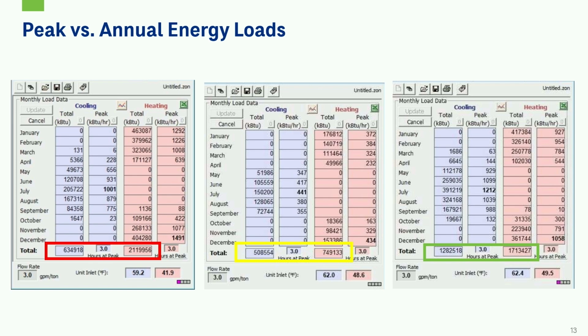Any other questions before we move on? All right. Okay, so when we use GLD, it looks at every hour of the building energy modeling loads, but it also gives us the monthly and annual totals and the peak hourly load for each month. So the peak loads are important, but the annual energy loads drive the size of the bore field and the amount of thermal drift over time.